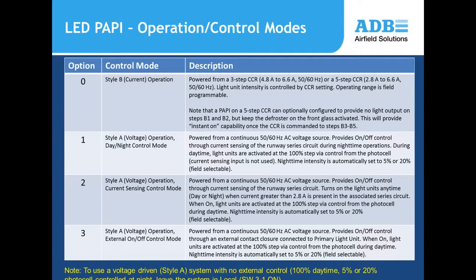Several operational control modes are available. The most common is simply turning on the unit. A current-driven PAPI operates at whatever step the constant current regulator is set to. A voltage-driven system has options such as photocell control — full intensity during the day, dropping to 5 or 20% at night — selectable in the field. The system can also be interlocked with a nearby series circuit so the PAPI only activates when, for example, runway edge or threshold lights are on.